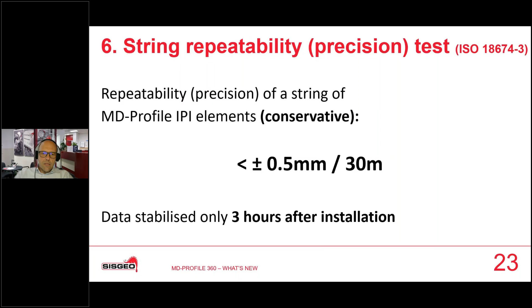What is very interesting and important is also that the data from our tests are stabilized just 3 hours after the installation. So if you go now at 3:20 to install your MD Profile chain, at 6:20 you can take your reference reading because the sensors are stabilized. Very good. These are some tests for the string repeatability that we do. And you can see that the worst curve arrives, for a 15-meter chain, up to 0.15 millimeter. So very, very, very nice.